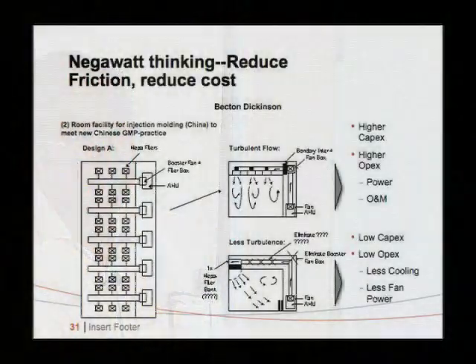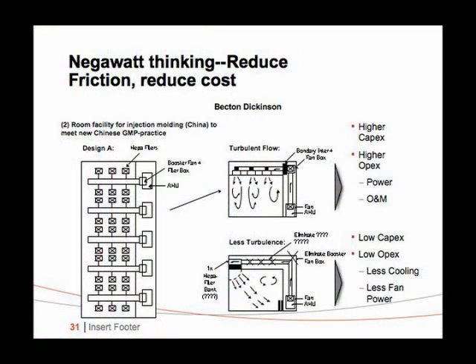We need to think in terms of negawatts. Usually you can do it with less. This is a project from China. Somebody had a clean room which had air handlers at the wall. And Chinese, I'm not picking on Chinese companies. The thinking is kind of linear. We will do filters the way we've always done filters, right? So many square feet, one filter box. Whatever the pressure drop is, we can handle because we know where to buy fans.